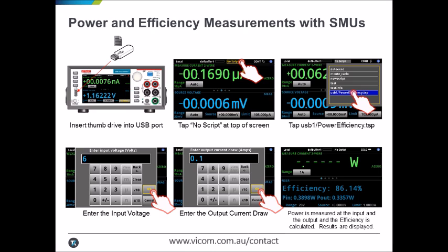This simple script handles most of the setup work for making the measurement and only asks for two pieces of information from the user. Enter the input voltage to source into the device, then enter the output current to draw from the device.